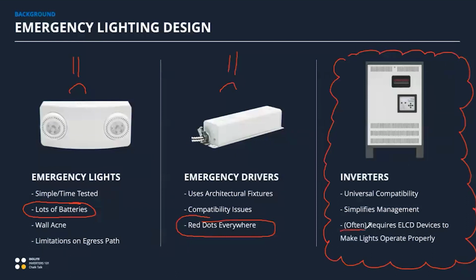One note, and I wrote the word 'often' here very intentionally: most inverter-based systems are going to require a little bit of additional hardware. Remember, that inverter is just a big box of batteries, so it doesn't really have anything to say about what the fixtures will do in an emergency, or about determining that there's a localized emergency at some location in a building.